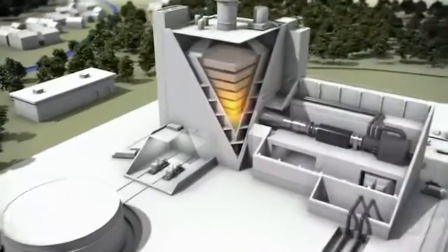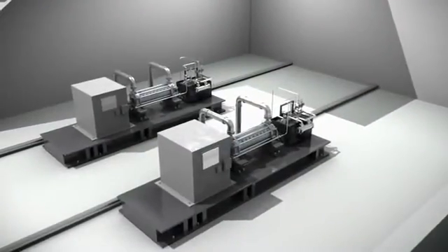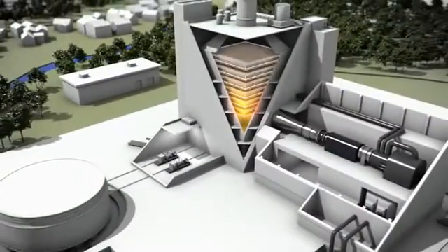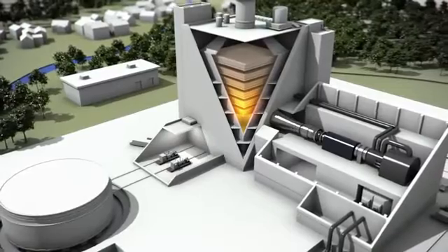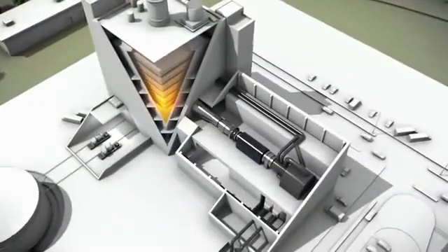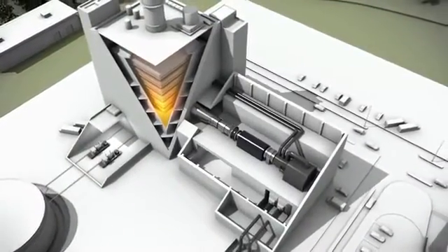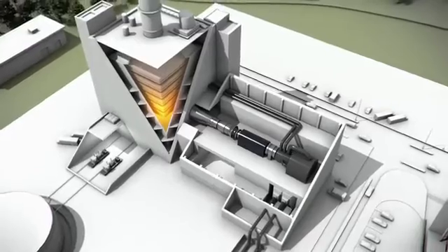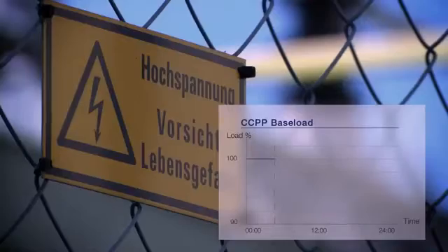Boiler circuits are an important component in power plants. Electric motor-driven pumps transport water into the boiler, where it is heated up by the gas turbine exhaust. The steam produced in this way is conducted through a steam turbine that, together with a gas turbine, drives a generator that produces electrical energy. Because of the high backup reserve requirements, even baseload power plants always operate with throttled boiler feed pumps.